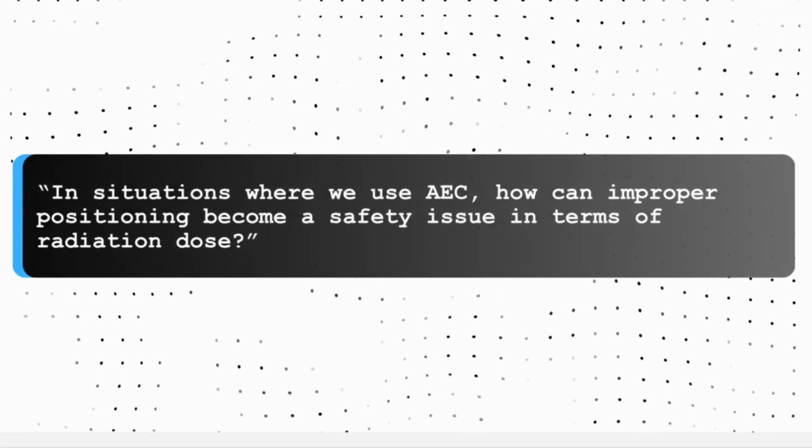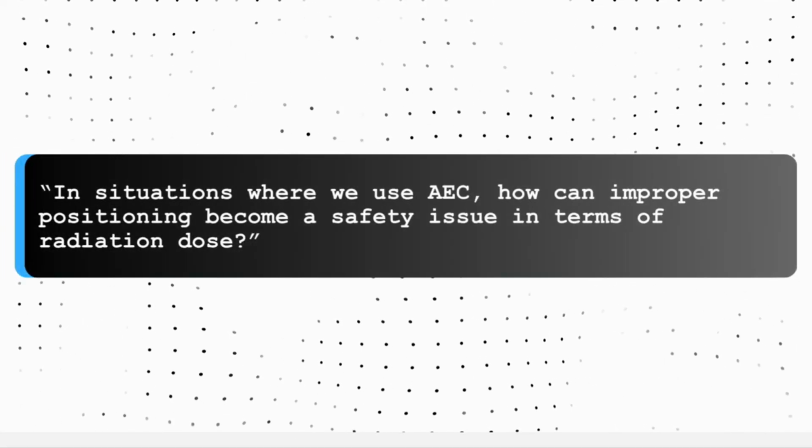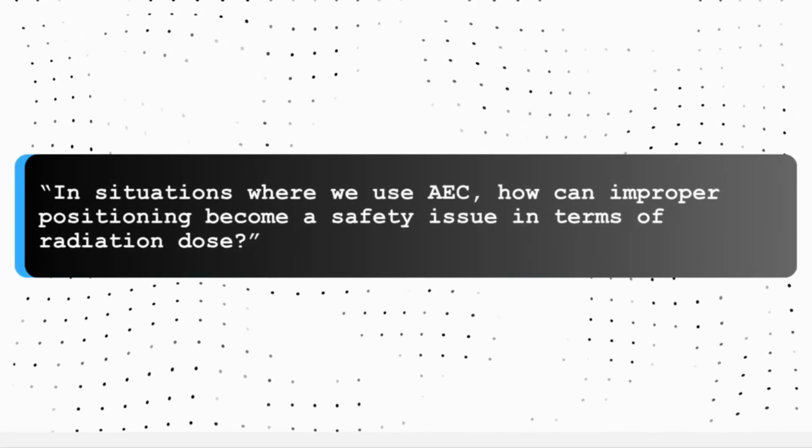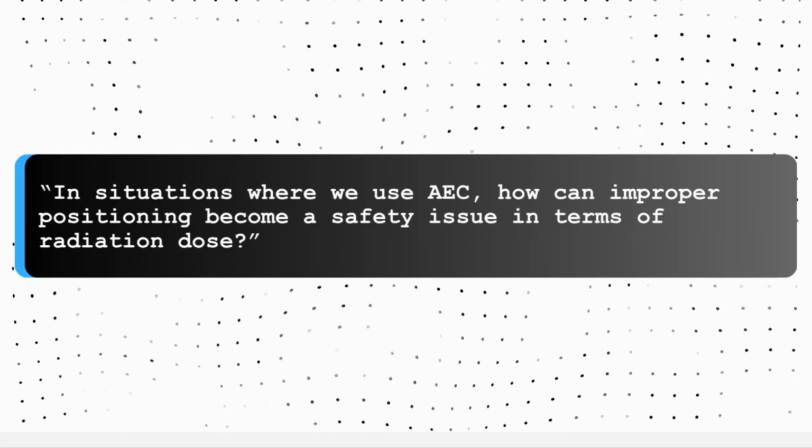So the question comes from Nia, the next question. In situations where we use AEC, how can improper positioning become a safety issue in terms of radiation dose? So AEC is a wonderful system in terms of keeping consistent exposures and making quality radiographs. However, it does depend on the radiographer selecting the correct chamber and making sure that they position the patient correctly.